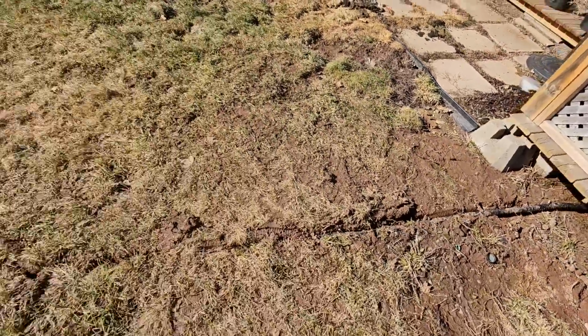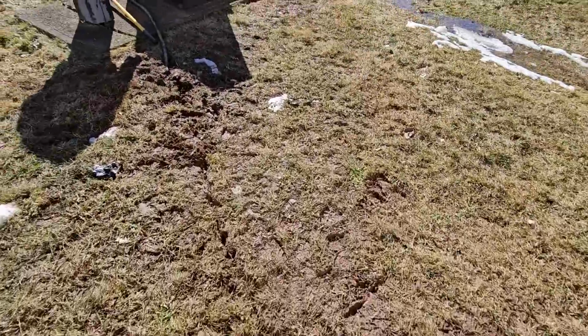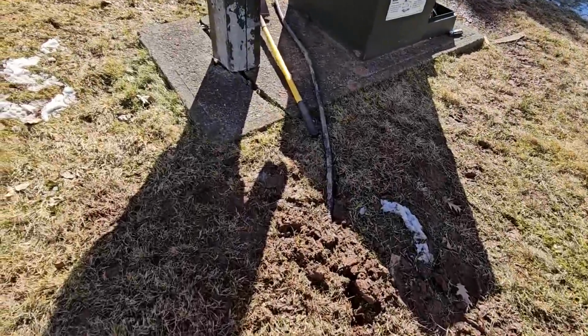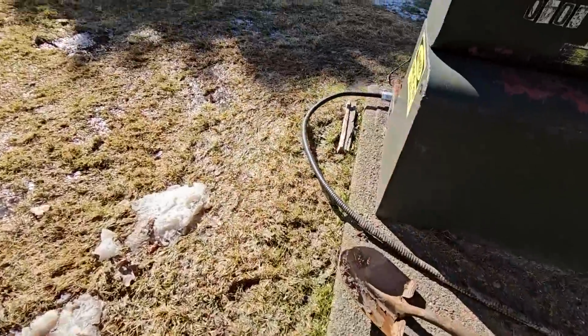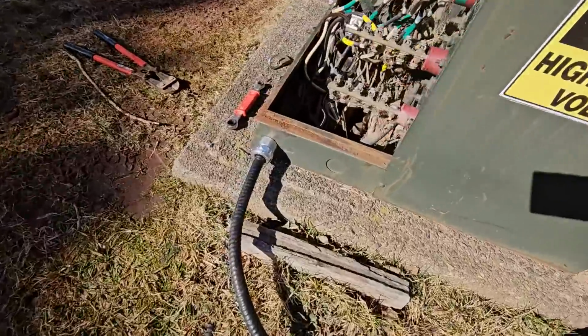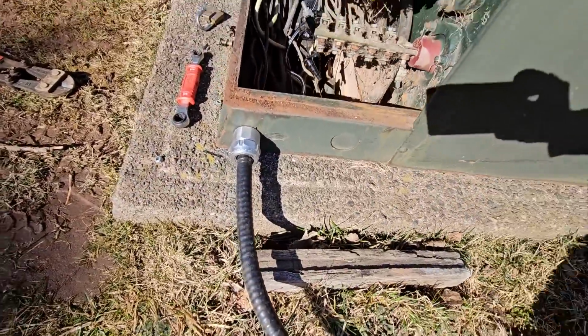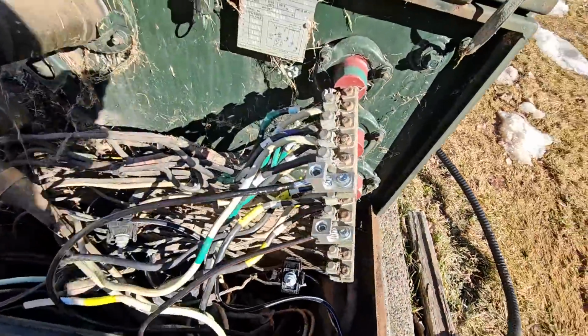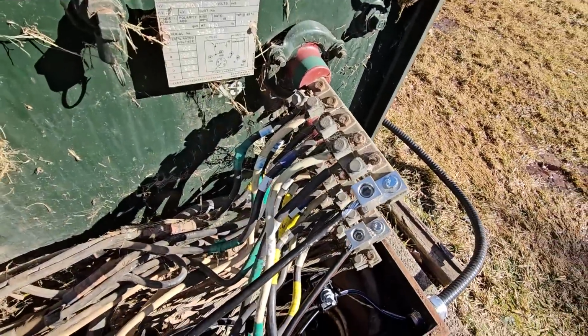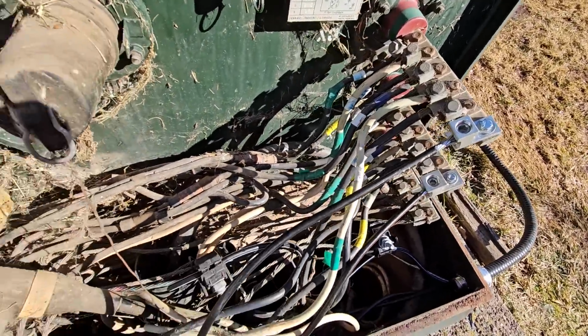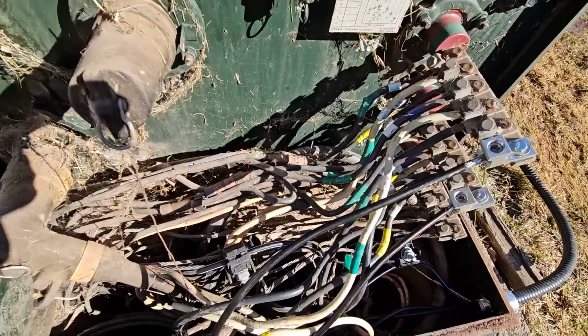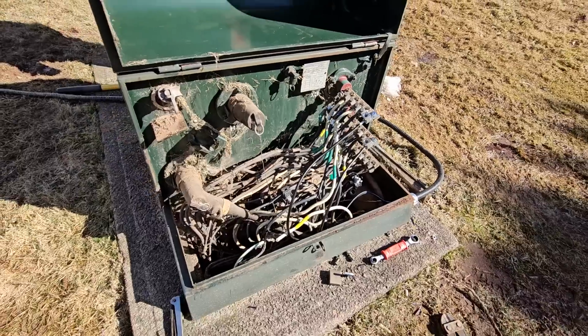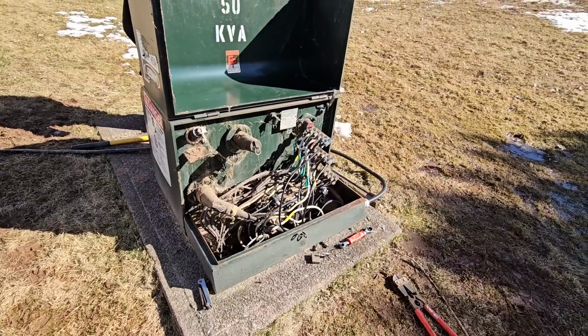So the biggest challenge with all these barriers - the frozen ground, the live wires - is the contractor's going to have to dig literally underneath this concrete pad to shove a PVC pipe up inside. And as you saw with the mess of wires, there simply is not enough room. Old standards, probably 50, 60 years ago, these services were all installed direct buried, so they're just coming out of the mud, shoving up inside.